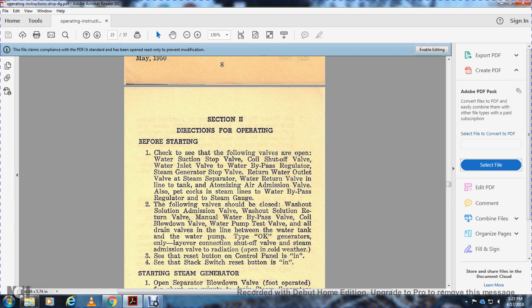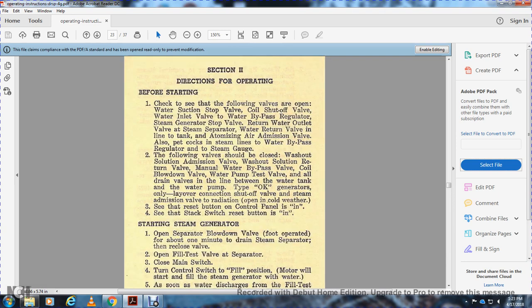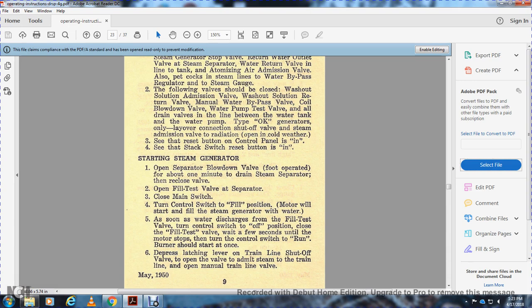So the reset button on the control panel is in. See that the stack switch reset button is in. Start the steam generator. Open the steam separator blowdown valve with the foot-operated lever for 1 minute to drain the steam separator, then close the valve.